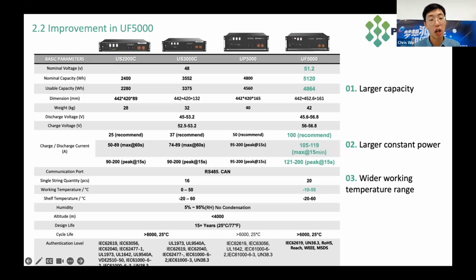Then we will check the charge and discharge current. For 0.5C batteries, the current will be half of the capacity, which means 25 ampere, 37 ampere, and 50 ampere. But for UF5000, the charge and discharge current can reach 100 ampere. So this means it can provide larger power at the same usable capacity, and it can also support larger max or peak current in an emergency case.